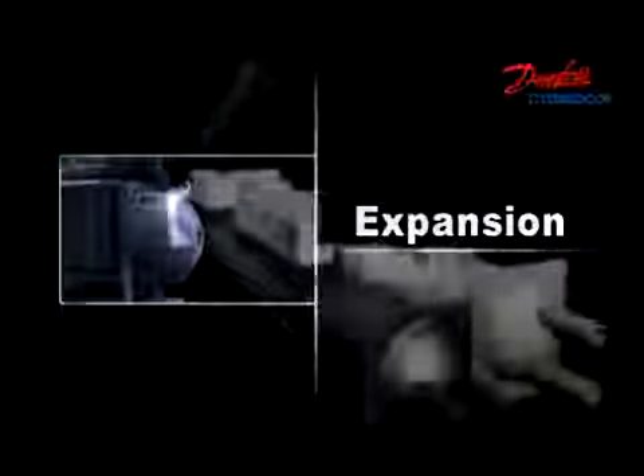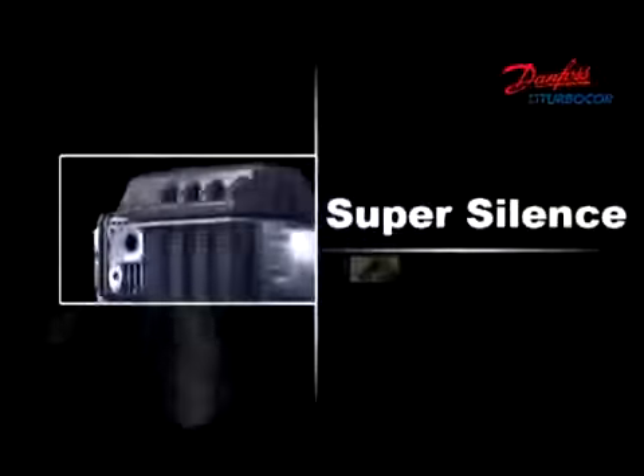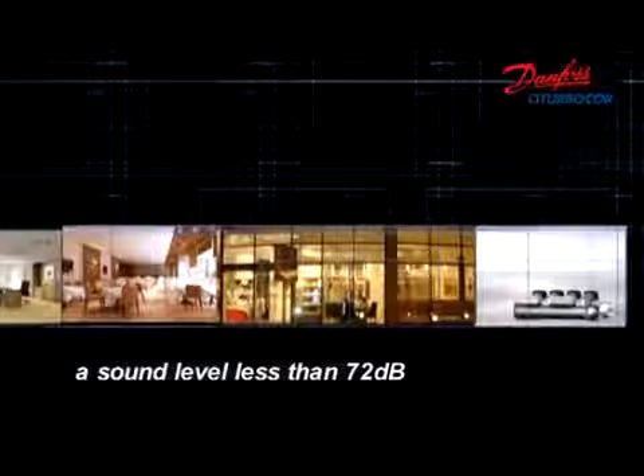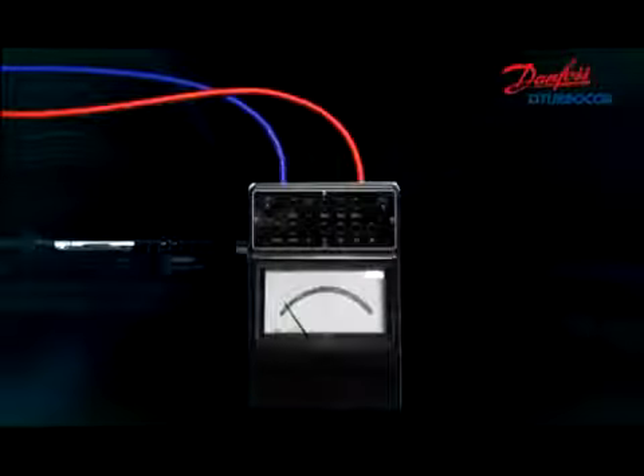It's very convenient to realize modularization with Turbocore compressors so as to satisfy the needs of larger capacity applications. Thanks to active vibration suppression control, there's no structure-borne vibration and less gas pulsation. Chiller can operate with a sound level less than 72 dB, which makes it possible to maximize the business value of many commercial buildings. Danfoss Turbocore only draws a few amps to start, which lowers the inrush strike on the grid and therefore reduces investments on electrical protection.